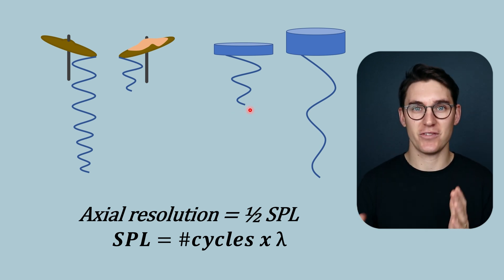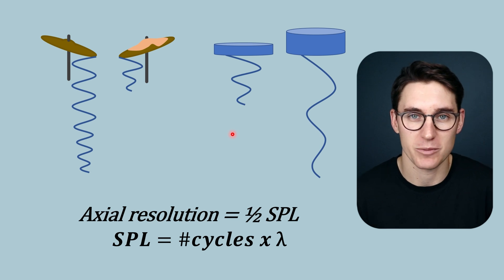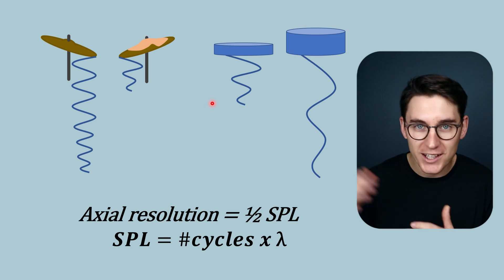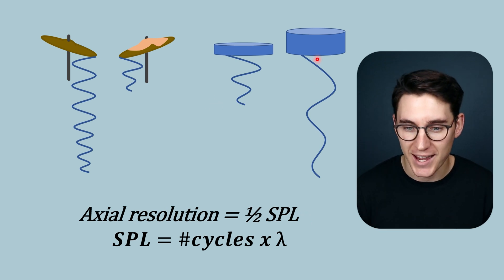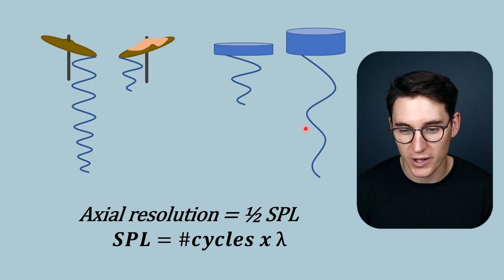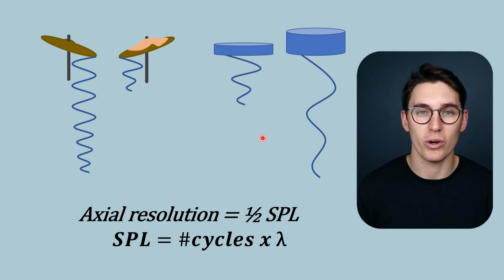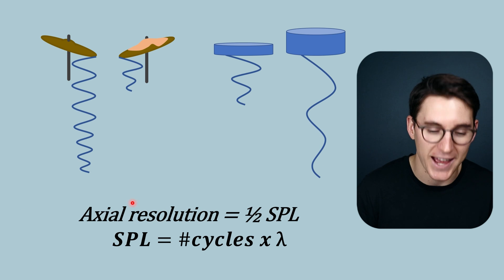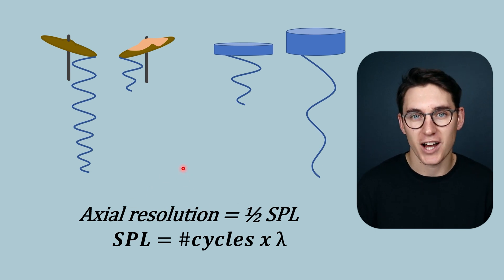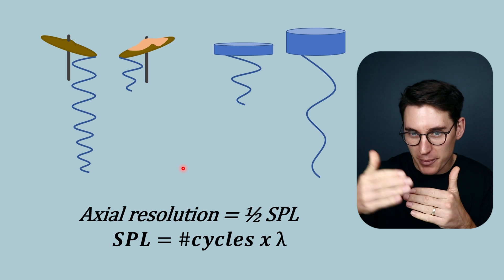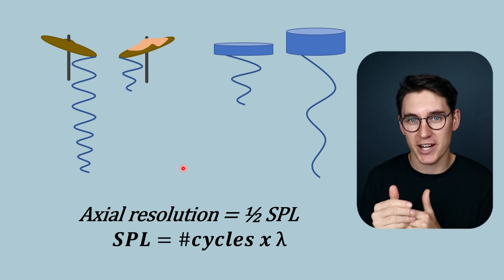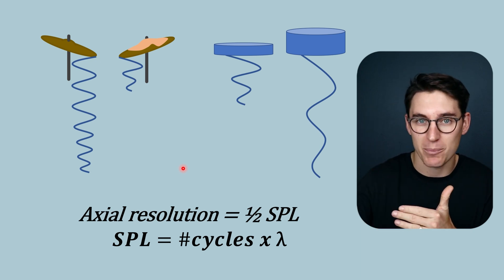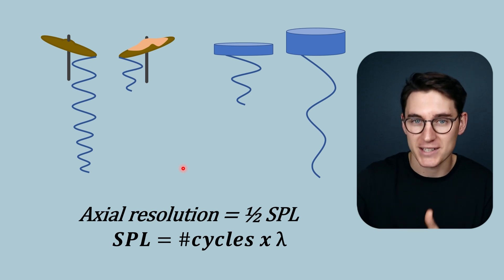In a specific tissue, wavelength and frequency are inversely proportional. As we reduce our wavelength by reducing the thickness of the piezoelectric material, we increase our frequency. A thicker piezoelectric material gives rise to a longer wavelength and subsequently a lower frequency wave. So higher frequency waves give better axial resolution. The higher the frequency of the ultrasound transducer, the better the axial resolution — though this comes at a trade-off, since high frequency ultrasound probes attenuate quickly and we get less depth in the image.